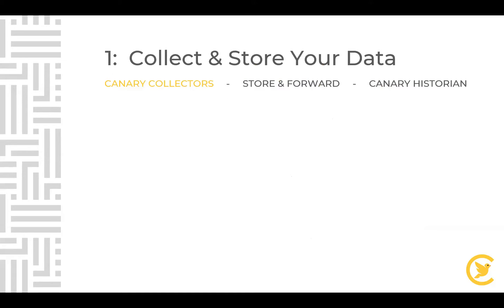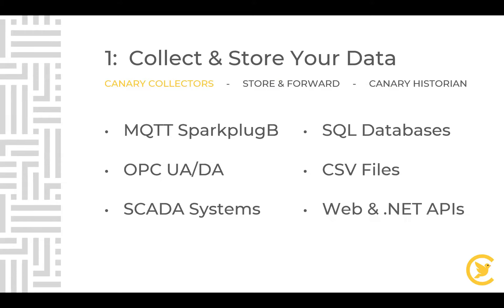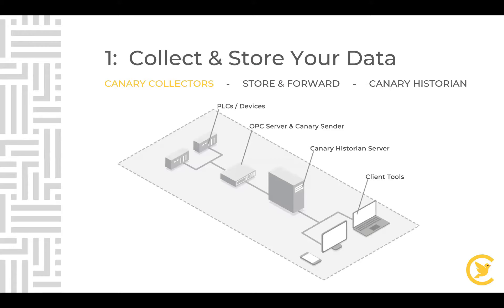Starting with Canary Collectors: Canary Collectors help you reach out to all industry-standard protocols so you can log data directly from your process into our system. Collectors can include MQTT Sparkplug B, OPC UA or DA, SCADA systems, SQL databases, CSV files, and Web and .NET APIs that allow you to create your own custom collectors. A typical architecture would have your PLCs and devices in the field communicating through an OPC server or MQTT broker, with our collector software installed on the OPC server and a Canary Historian server that client tools connect to.